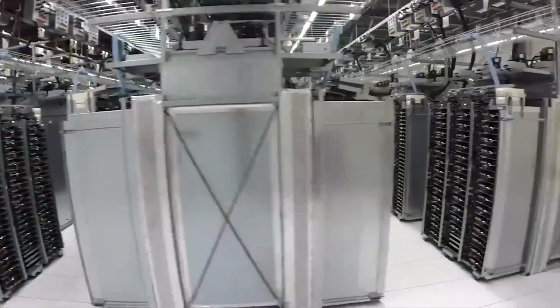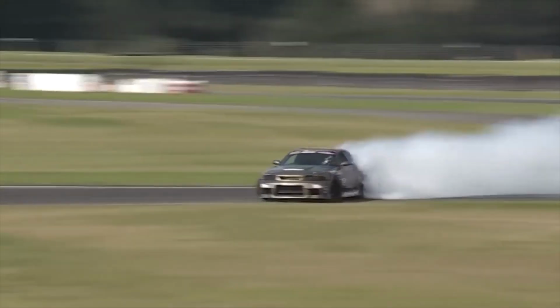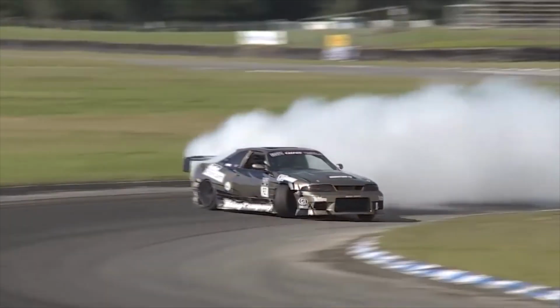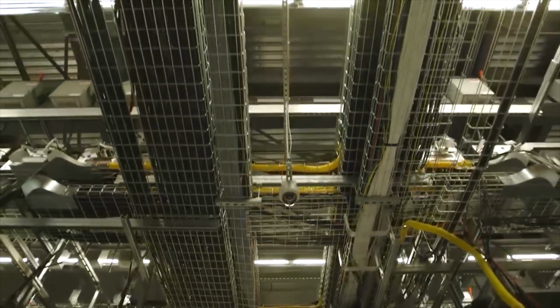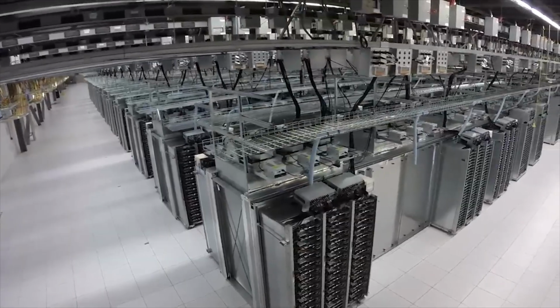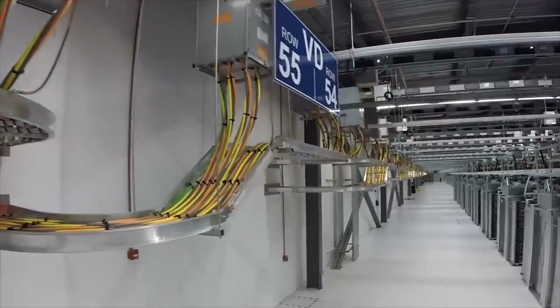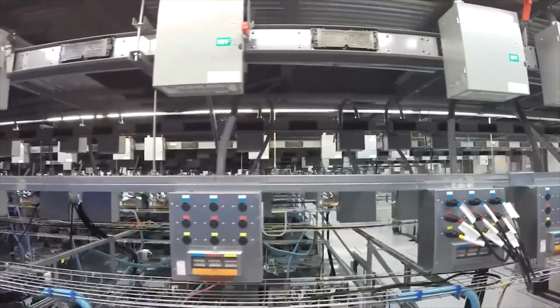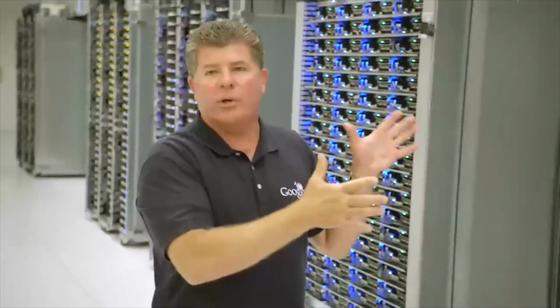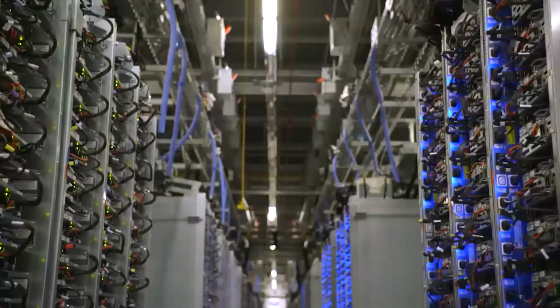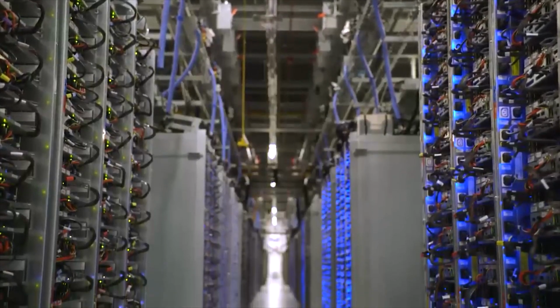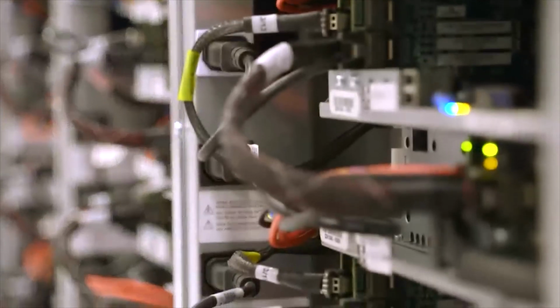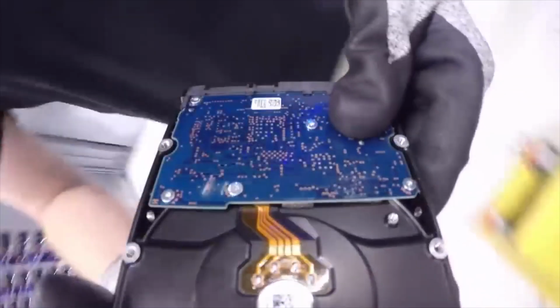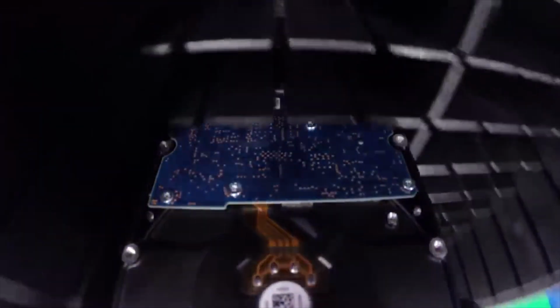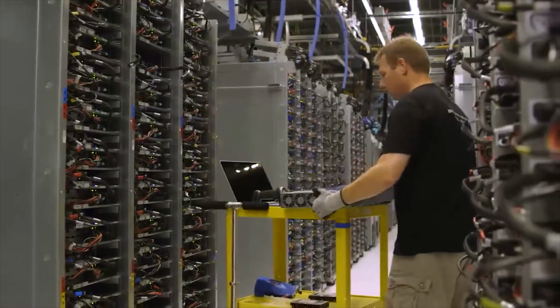Google's servers are stripped of unnecessary components. Think of a race car built for speed, not comfort. This lean design maximizes performance per watt, squeezing every drop of computing power from each unit of energy. Google's power usage effectiveness, PUE, a key metric for data center efficiency, hovers near 1.1. This means for every watt used to run servers, only 0.1 watts go to cooling and overhead. Compare that to the industry average of 1.6, and it's clear Google is in a league of its own.